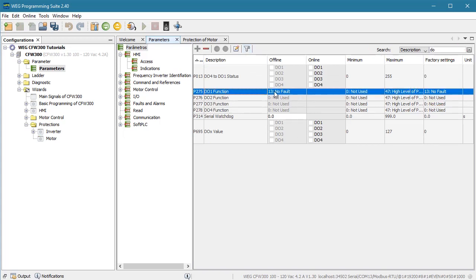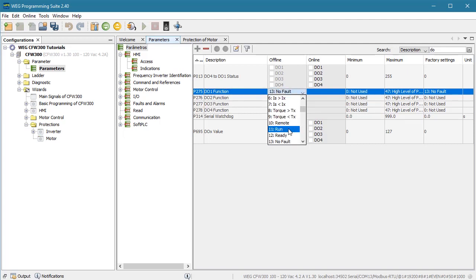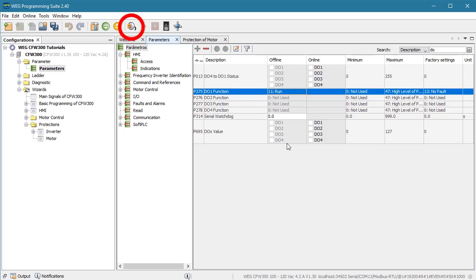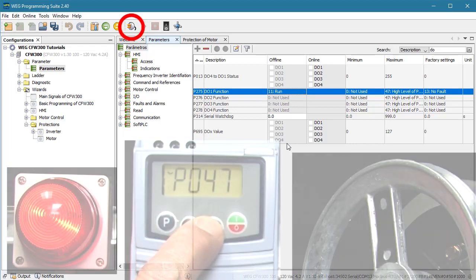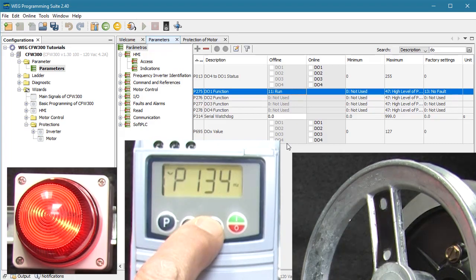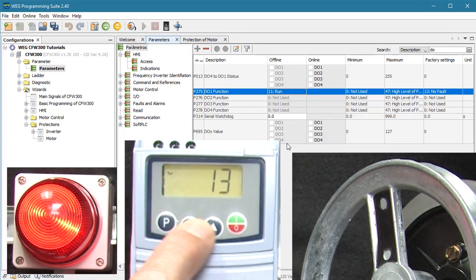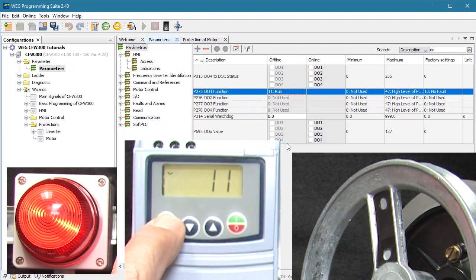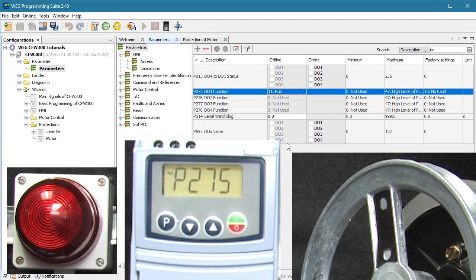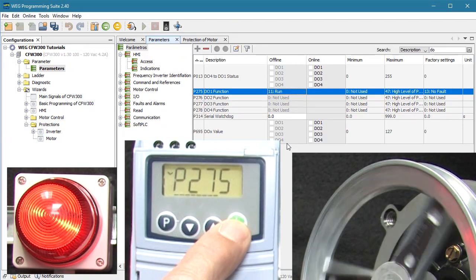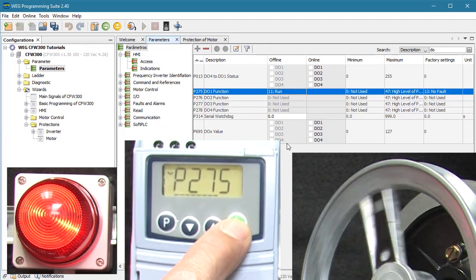How about we change Digital Relay Output 1 to indicate when the drive is running? Looks like we need to put an 11 in parameter 275. This software isn't currently connected to the drive, so I'll go to the drive, scroll to parameter 275 and enter an 11. When I hit run, sure enough our new run indicator lights up.